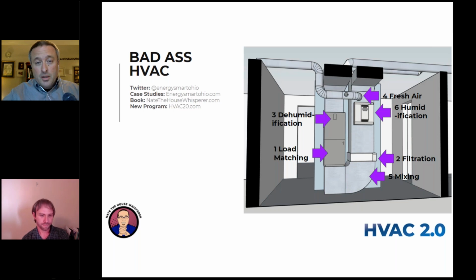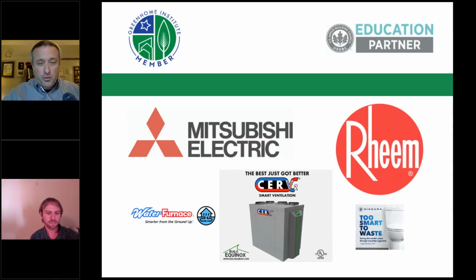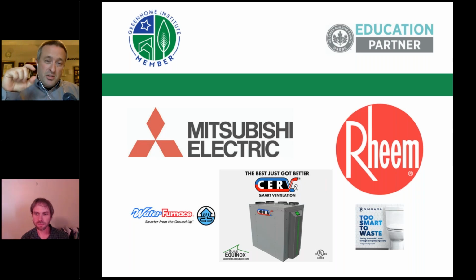Yes. On high, a lot of systems are going to be at least a little bit noisy. Most existing homes really don't have much more than 3 tons of ductwork, so they can't handle more than about 1,200 CFM of flow. That's part of why we try to aim everything to be a 3-ton system, so it's not crazy noisy running flat out. But the beautiful thing about variable speed equipment is they're probably mostly going to be running at 25, 40, or 50% of capacity, and they're just not that loud.